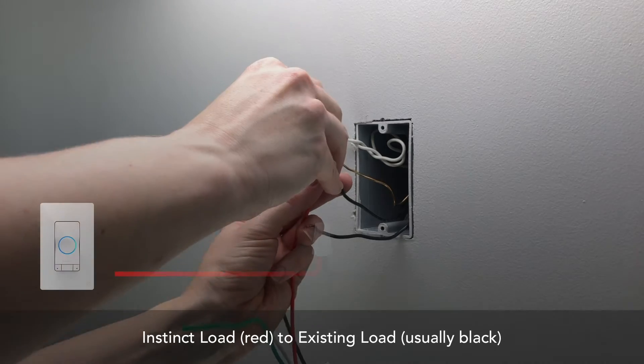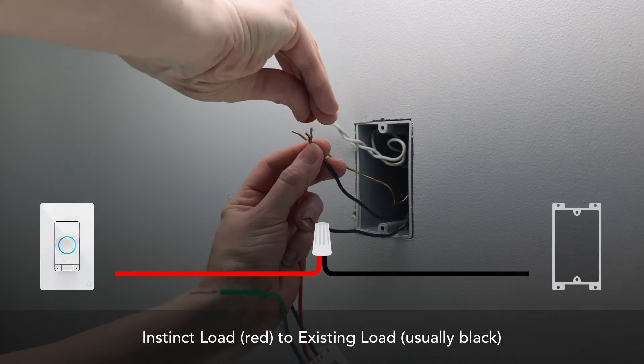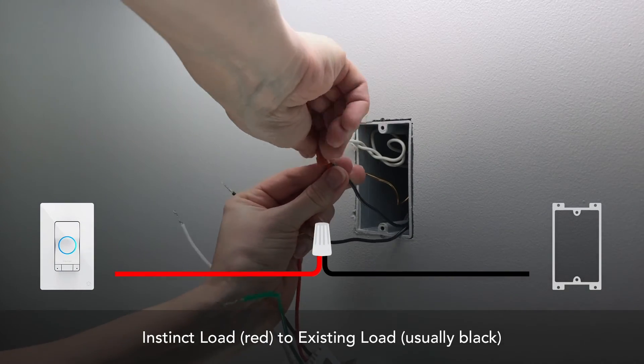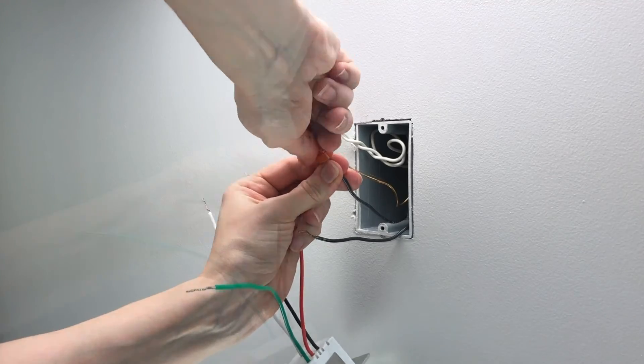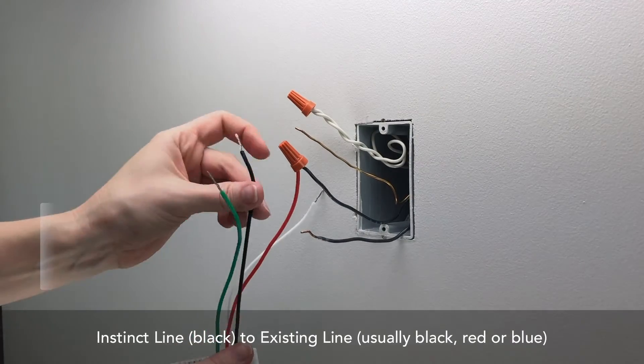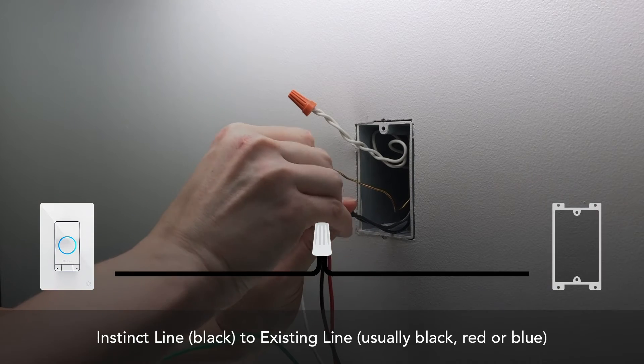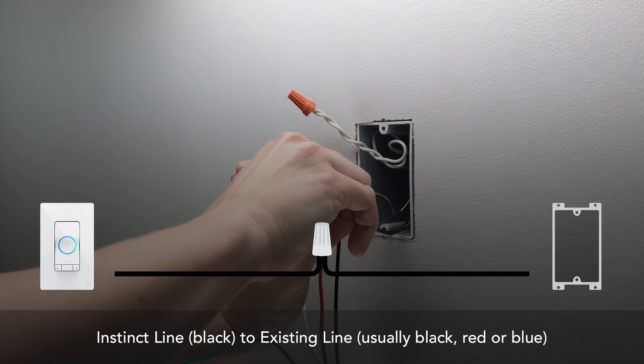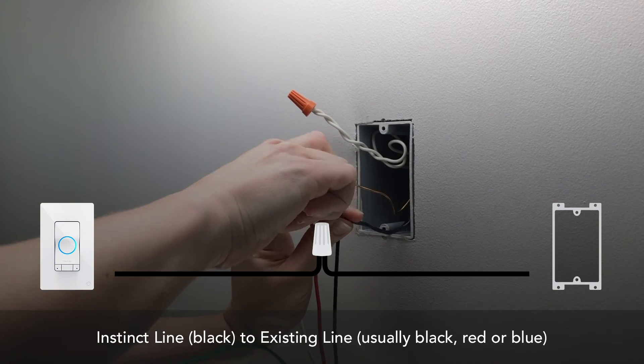Connect the red load wire on Instinct to the load wire you removed from the previous switch. Connect the black line wire on Instinct to the line wire you removed from the previous switch. This was the energized wire you noted previously.